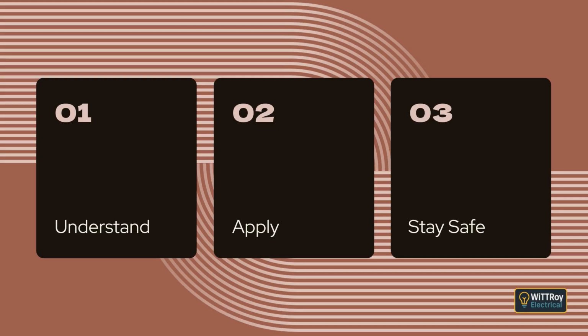Clause 4.1.4, Adverse Effects and Interference. This clause explains that equipment must be chosen so that during normal operation, including switching, it does not cause harmful effects to other equipment. When selecting equipment, we must consider issues such as poor power factor, excessive voltage fluctuation, distortion of current waveforms, or electromagnetic emission. These effects can interfere with other equipment or reduce performance. The goal is to make sure the installation operates smoothly without one appliance disturbing another, and this is achieved by good equipment selection and proper installation.